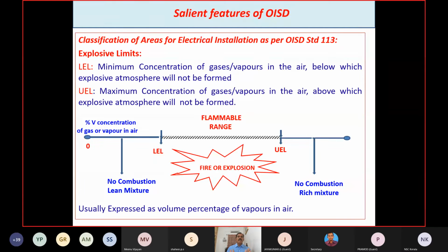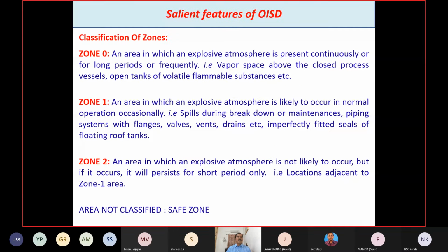So if it is within the flammable range, that is between LEL and UEL, and it comes in contact with any source of ignition, it will result in fire or explosion. So the fire risk is higher, but the level of fire risk mainly depends on the frequency and duration of occurrence of such a flammable atmosphere. Hence it is very essential to analyze the area zone-wise. So let us see how the zone classification has been done.